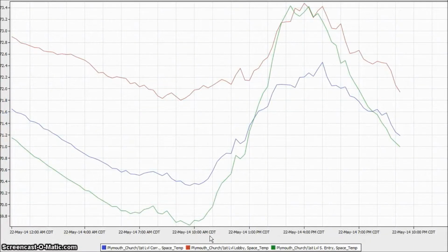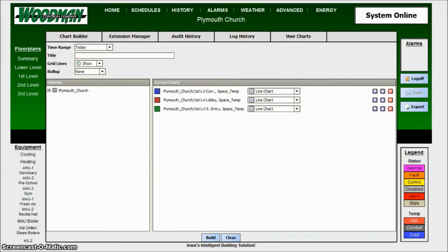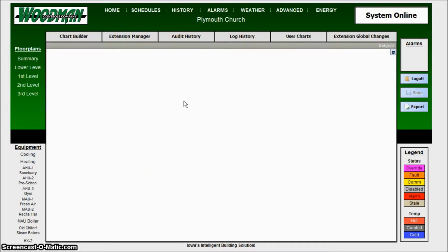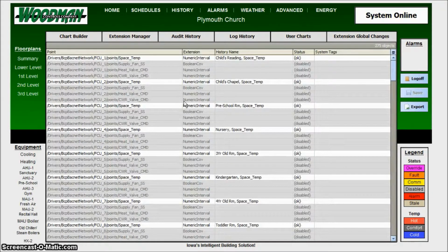For example, maybe you want to trend outside air temperature versus hot water supply temp and chill water supply temp, and you really want to be able to see what that system's been doing and how they're reacting to that outside air temp. The extension manager, and again we'll do this in a little bit more advanced video, is looking at all the history extensions in the system. So every physical point in the system is typically how Woodman does it.